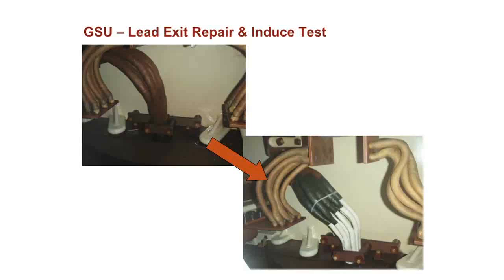This is a lead coming out of the winding. It's a little hard to see here in the picture, but this is a lead coming out of the winding, and there was a lot of serious overheating on this winding exit lead. Otherwise, the transformer was fine. This was only the one part that was calculated to show very high temperatures here. So then, going inside the transformer, everything was untaped, and then it was taped with a high temperature tape. And then you took away that thermal risk. So again, this is just an example of things that can be done inside a transformer.